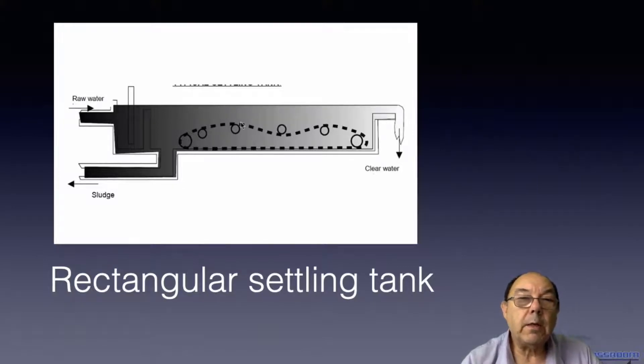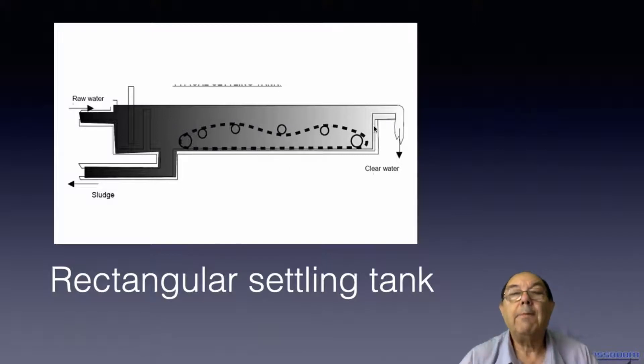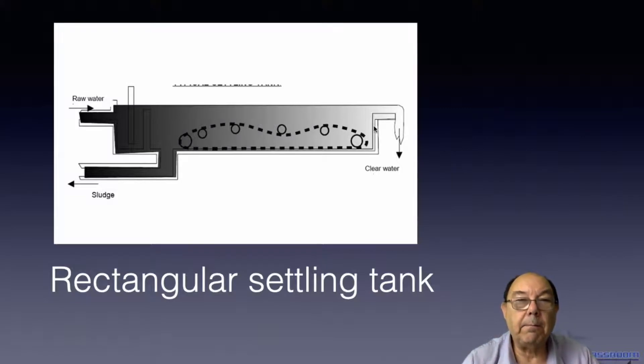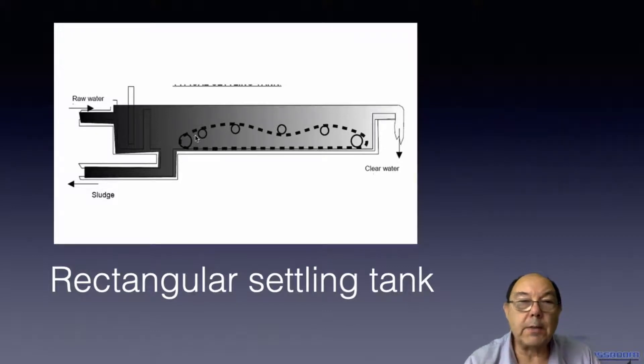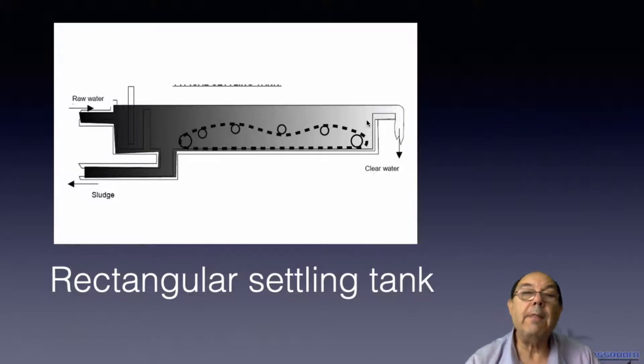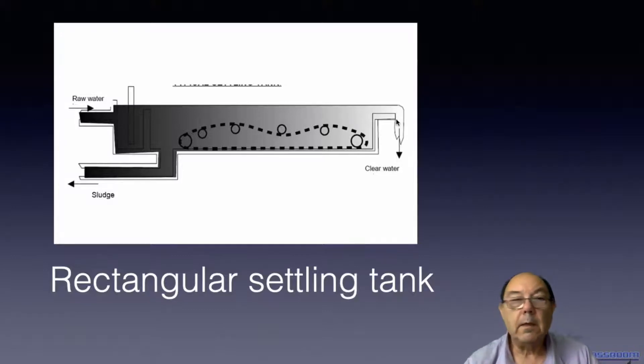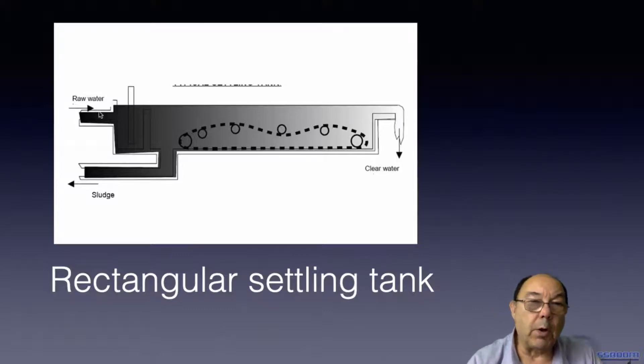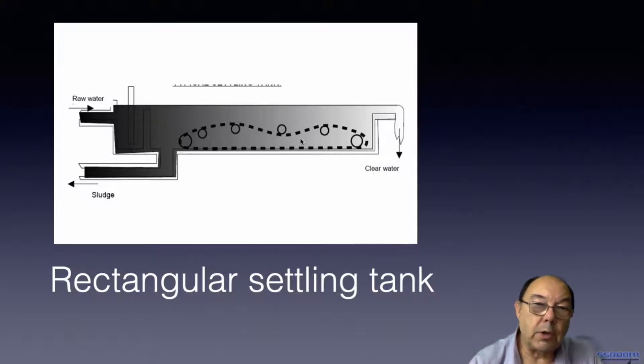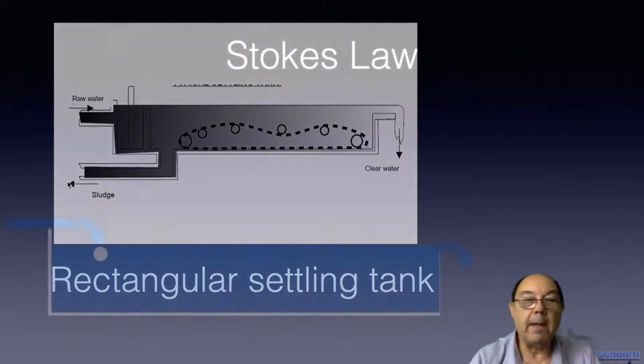When you are designing these tanks and calculating the length, what you need to know is what's the smallest particle that you need to settle. Then you need to calculate the flow rate so you know how long it needs to travel until it gets below the weir, and then you can calculate this particular length. The raw water comes in here, it settles, and this mechanism drags the sludge down and then that's treated.